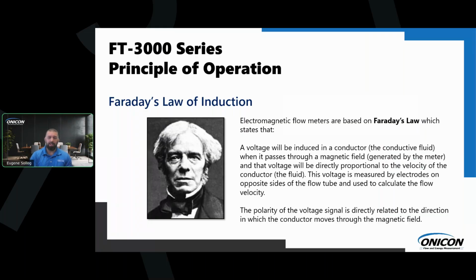This voltage is then measured by electrodes on the inside of the meter, on opposite sides of the flow tube, and that's used to calculate the flow velocity. So we're measuring flow velocity with this meter. The polarity of that voltage signal is directly related to the direction in which the conductor moves through the magnetic field. So this meter, by nature, is a bidirectional meter, just like both of our insertion mag meters.